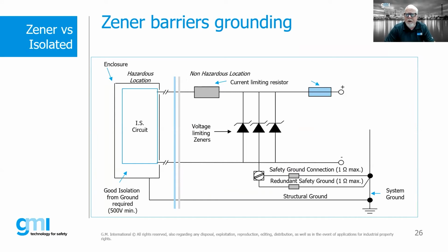So here's an example of, again, how we might typically ground Zener diode barriers. So notice that there's actually a safety ground connection, and we might have a redundant safety ground because it is a requirement that we want to test to see, is our ground still maintaining 1 ohm max resistance over time, right? We may have a degradation. So the way we would actually have to test that, we'd have to remove one of the legs and test it. We don't want to test it and all of a sudden introduce a fault condition into a barrier system. So it's not uncommon to have actually a redundant safety ground. So we'll disconnect one of those legs, test the resistance on that particular ground loop, and then do the same thing on the standard one, disconnect it, and then go ahead and check it. And again, tie that into our system ground.